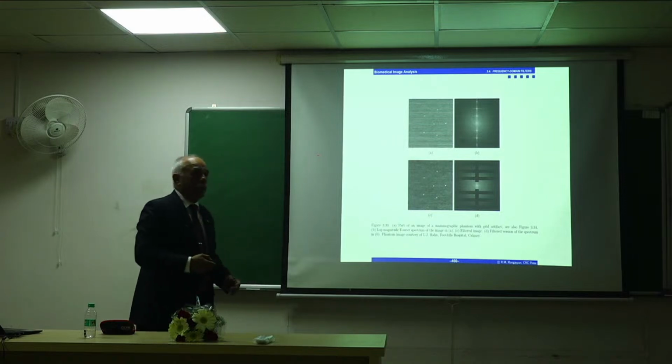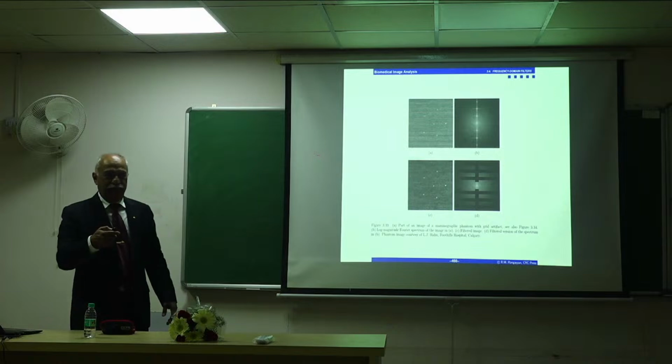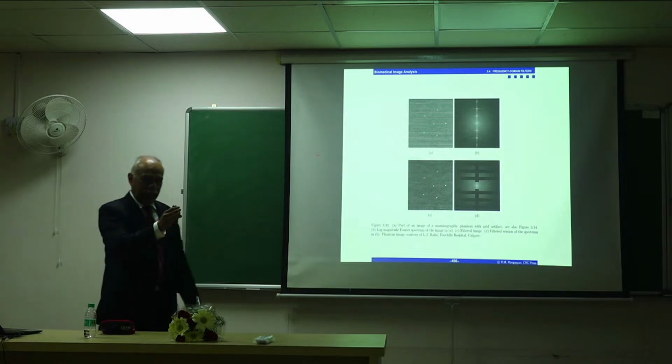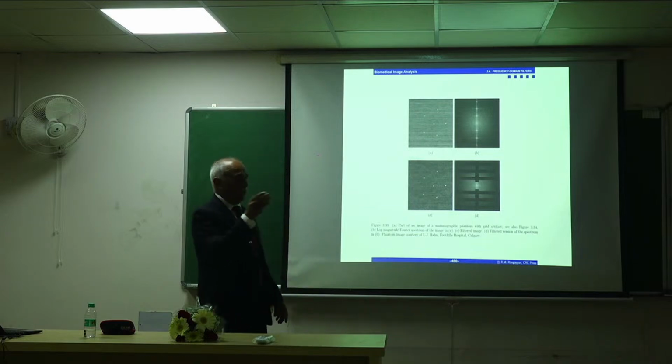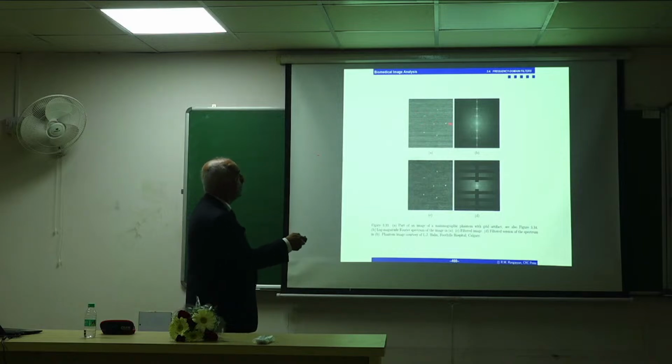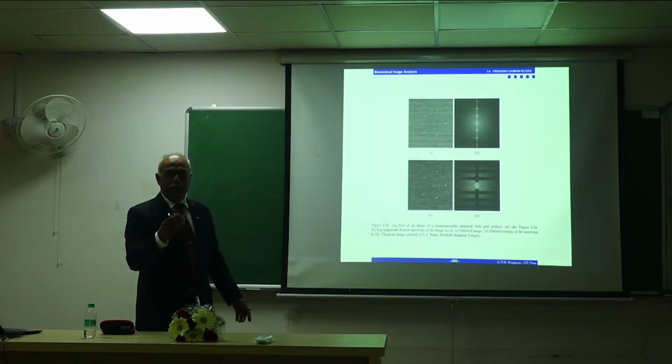I asked Dr. Hahn, my colleague in nuclear medicine, to take a picture of this phantom with and without the grid moving properly. The grid has to move during the X-ray image acquisition procedure to get a smooth image, to reduce scattered photons and scattered noise due to scattered photons. But if it doesn't move, you get these lines. Those are the grid lines. And these bright spots are the calcification simulating material in the phantom.